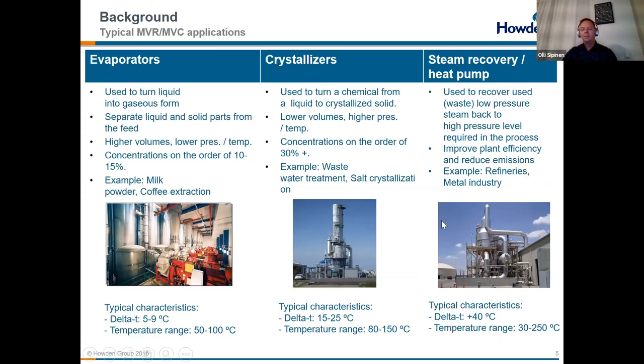And then we have the one closest to today's topic: how to recover the steam pressure to a usable pressure, in this kind of heat pump type application. There the delta Ts, which are required, can be very, very high, as we have seen. Depending on the site design, 3 bar, 6 bar, 8 bar, we have seen even higher requirements, and thus the temperature range to work in starts from really low vacuum, and what pressure is then needed could be really high.